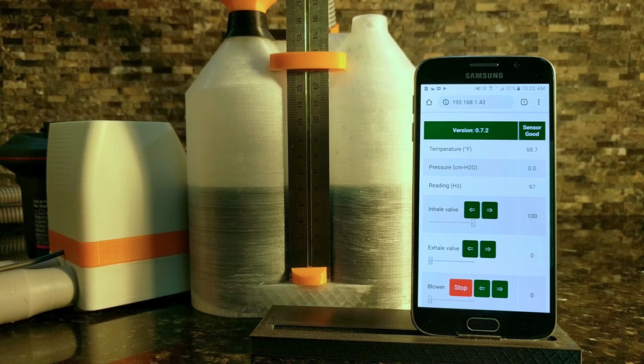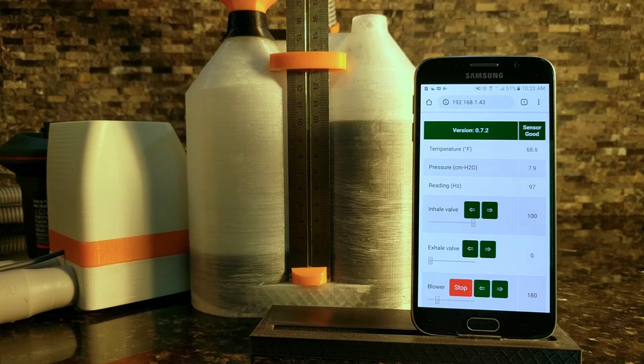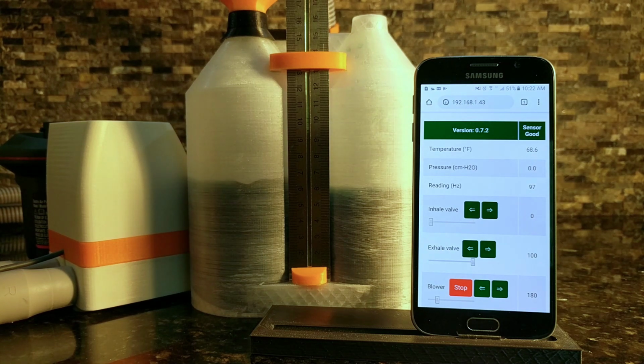In this demonstration, InqVent simply spins up the pump. You will see the blower spin up to 180. It will stabilize, and then it starts firing the valves to cycle between inhale and exhale. It will be on a 12 breaths per minute schedule. At the moment, it simply slams the valves open and then slams them closed. Subtleties of rates and holds are ignored at the moment, but again, this too will be added in the coming weeks. Here we go. As you can see, the pressure and volume defined by the relative water height shows InqVent is performing as asked. The user interface is also tracking the pressures and valve position.